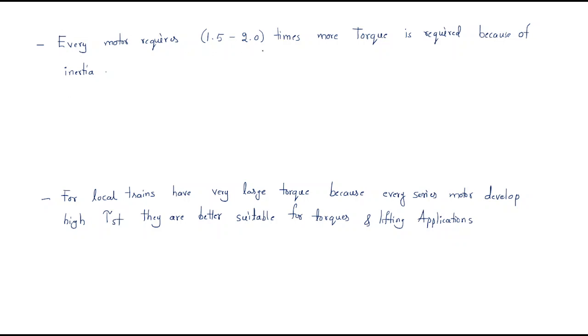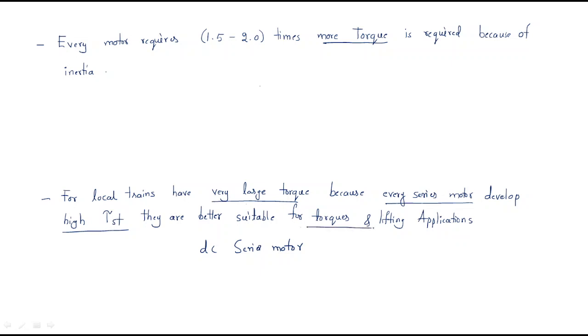Every motor requires 1.5 to 2 times more starting torque because of inertia. Local trains require large torque, and every DC series motor develops high starting torque. That is why DC series motors are used — they are well suited for traction and lifting applications, where high starting torque is required.